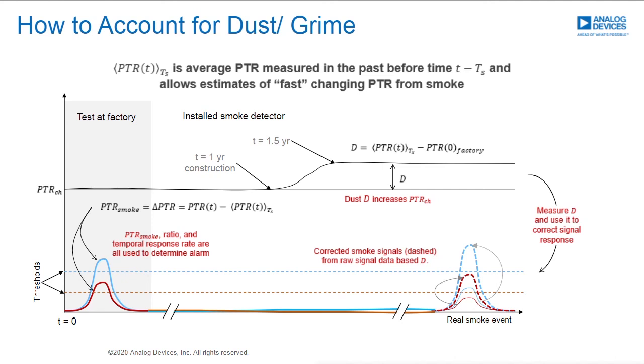Okay, one of the things that makes our design a little bit challenging is having to deal with the background response of the chamber. But once you've figured out how to deal with that background response, it actually provides you a lot of self-diagnostics of what's going on inside your smoke detector that otherwise wouldn't be available. For example, just to determine that your optics are working, it's a simple measurement right off the chamber and you can see that you're getting a signal. The other thing that you can do is measure how much dust is accumulating, or grime, right? So, if over time you're getting a lot of dust or grime accumulation, it may get to the point where you want to trigger an alarm for the user to either replace the smoke detector or open it up and clean it, right?